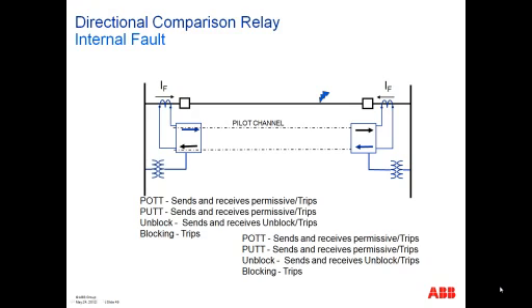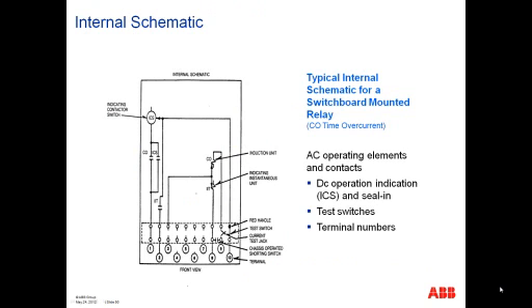And the blocking system does nothing in regard to sending any information, so they both see a forward fault and end up tripping. Now, those were the basic schemes, and what we're going into now is documentation, if you will, that you really need to use to analyze system faults.